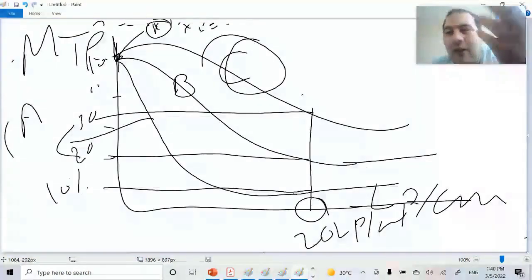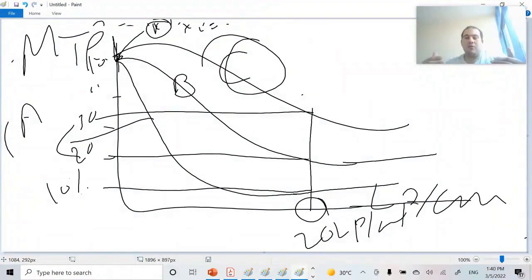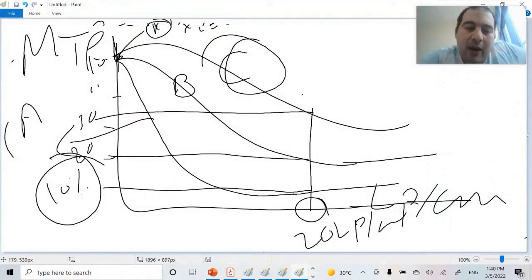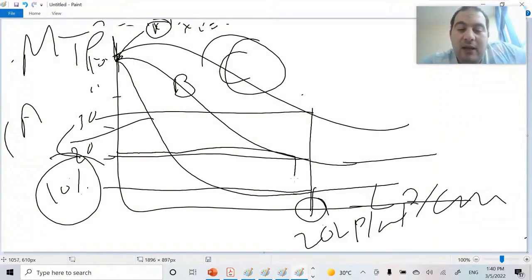The more the machine can see, the better. The standard you have to judge it by is 10% efficiency. I look at the 10% and see how many line pairs the machine can see. For example, it saw 20. In B, it saw more than in A, and so on. So at a certain value, the 10% at A saw, for example, 10 line pairs.